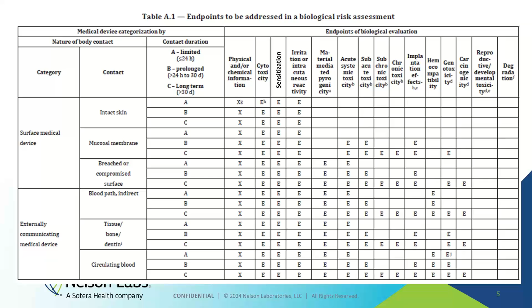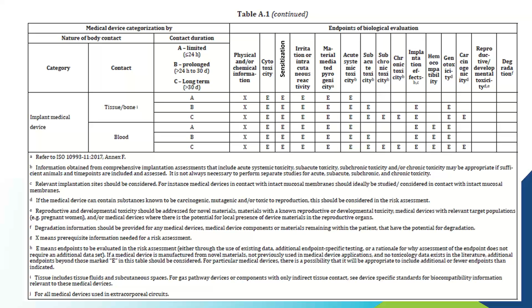But the main thing that has been changing is that in the table there are lots of E's, right? That was the big change from the previous version of the 10993-1 that was released in 2009 to the one released in 2018: all of those X's turned to E's, and the E means that the endpoint really needs to be evaluated in the risk assessment. Rather than just jumping into testing, you need to look at all of the available data, everything that we know about the materials and processing, as well as how your device is used, and then define: is the endpoint already covered with the available data? Does the endpoint even matter? And what type of testing, if at all, is needed to complete the data set for your specific device.